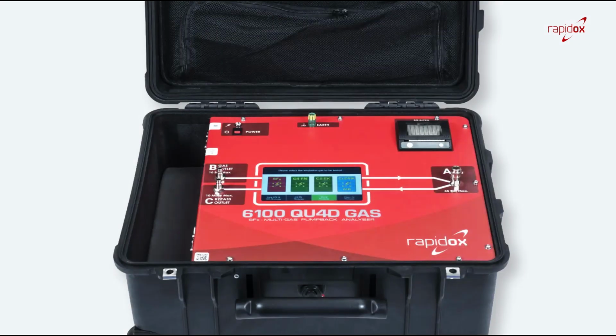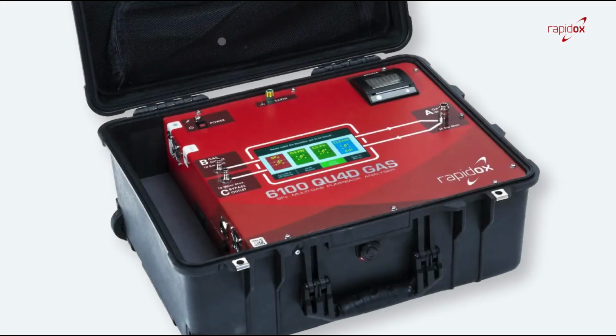So what I've got in front of me here is our latest generation SF6 Quad Gas Analyzer. This is a multi-gas analyzer that's designed for next generation SF6 alternative gases. It'll measure many different gases, including Novec type gases, C4, C5, as well as dry air, and of course SF6 as well. Okay, so we're going to start with an overview of the analyzer itself.